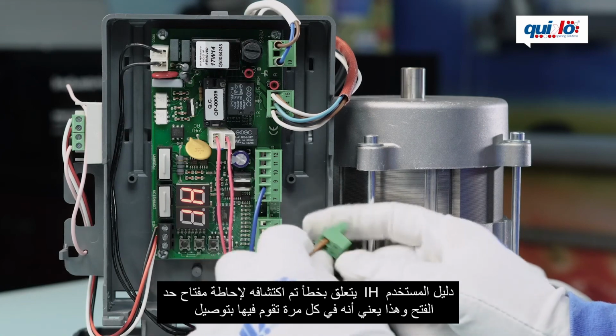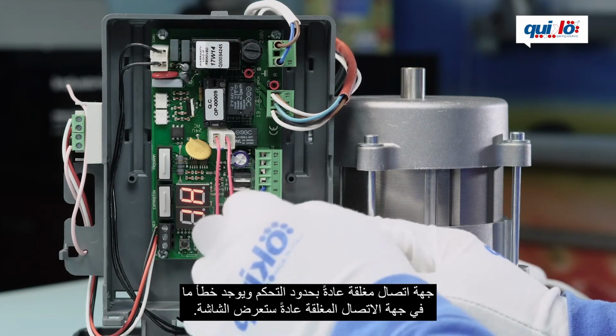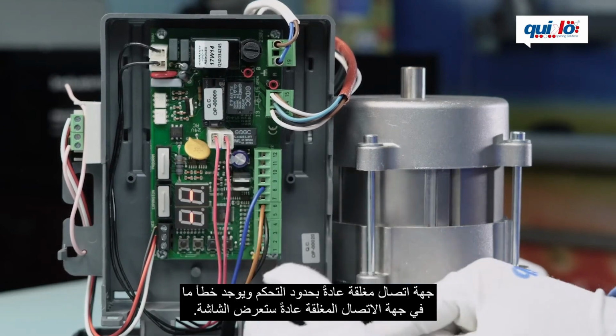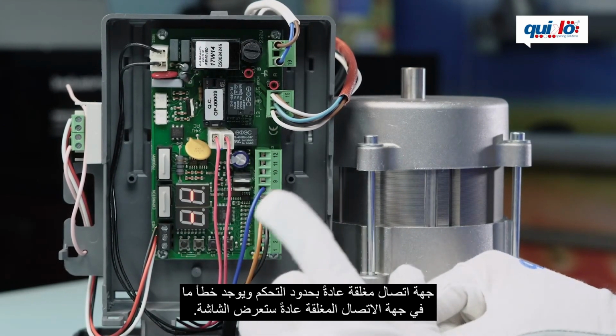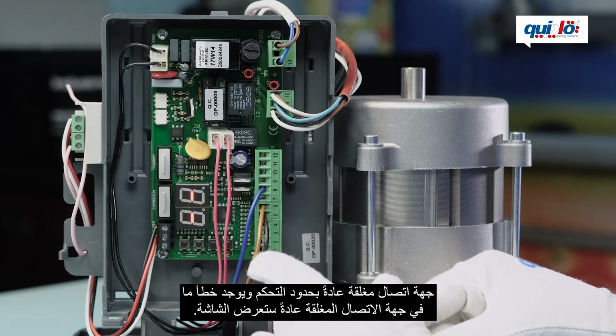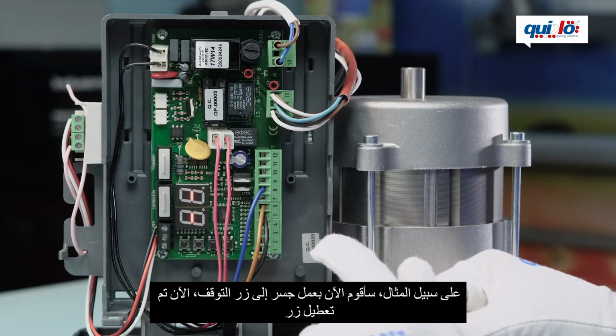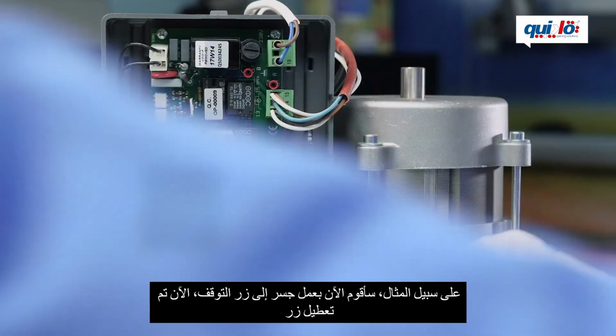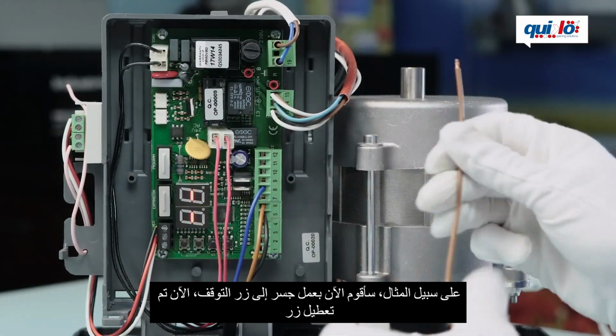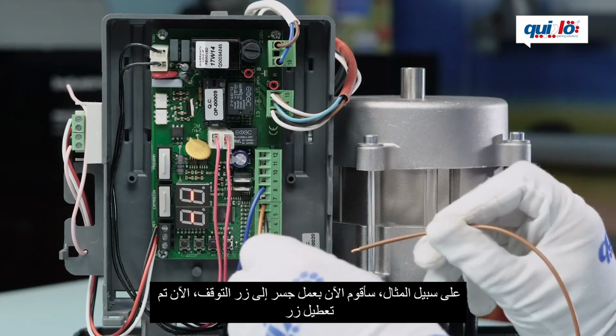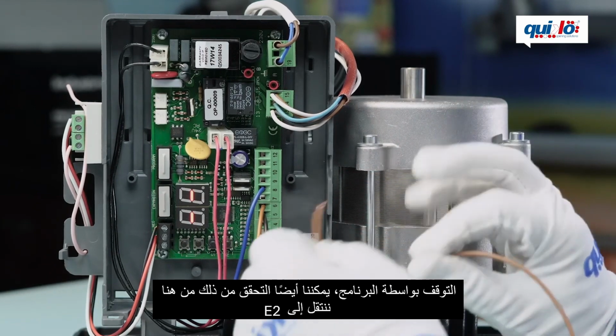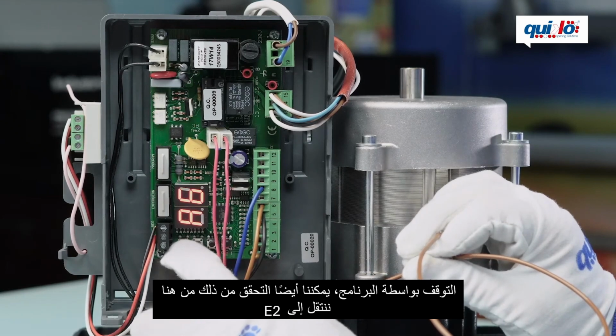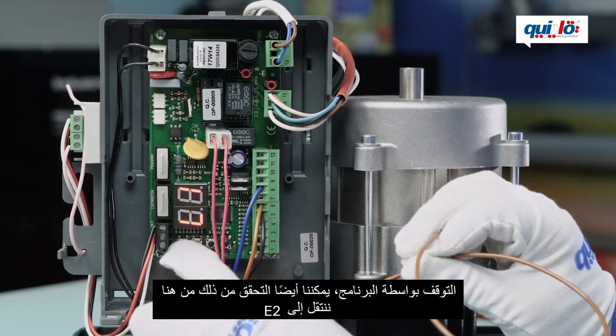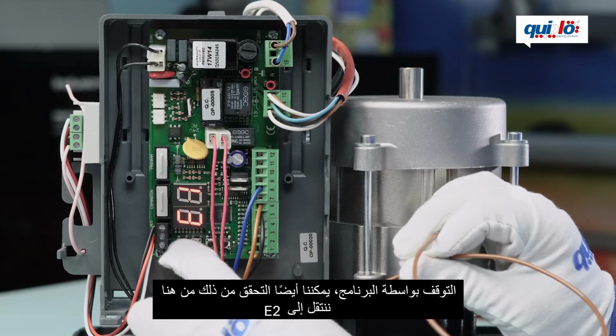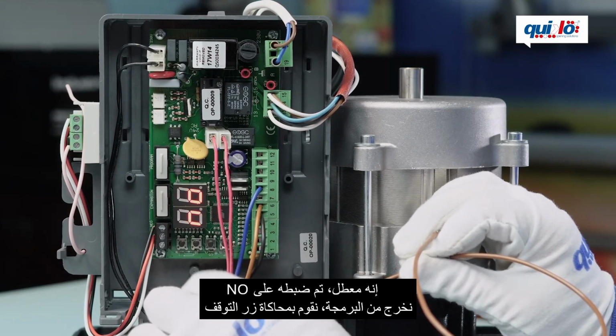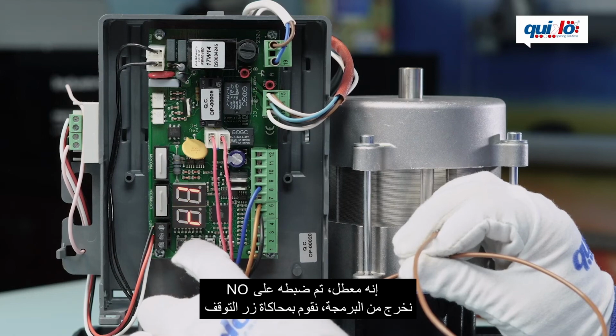This is to say that every time that you connect a normally closed contact to the control board and there is something wrong with the normally closed contact, the display will show it. For example, I'm going to now make a bridge to the stop push button. Now the stop push button is disabled by software. We can also check it from here. We go to E2, it is disabled, it is set to no. We go out from programming.